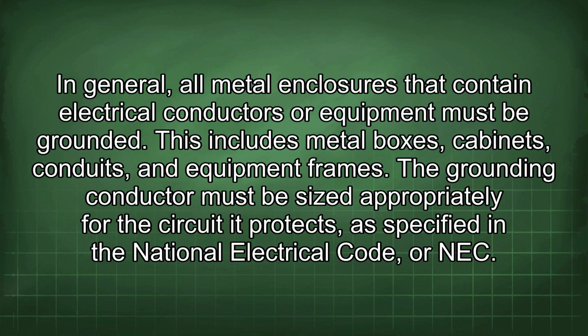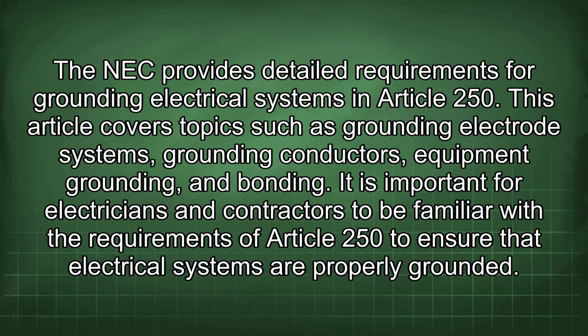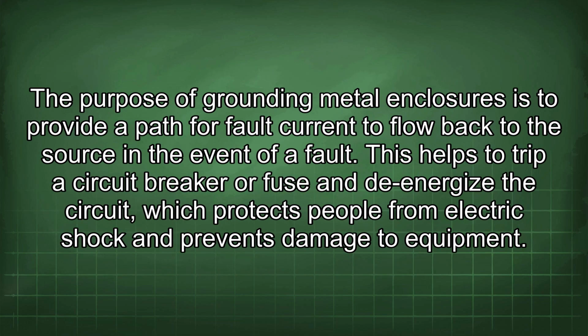The grounding conductor must be sized appropriately for the circuit it protects, as specified in the National Electrical Code, or NEC. The NEC provides detailed requirements for grounding electrical systems in Article 250. This article covers topics such as grounding electrode systems, grounding conductors, equipment grounding, and bonding. It is important for electricians and contractors to be familiar with the requirements of Article 250 to ensure that electrical systems are properly grounded. The purpose of grounding metal enclosures is to provide a path for fault current to flow back to the source in the event of a fault.